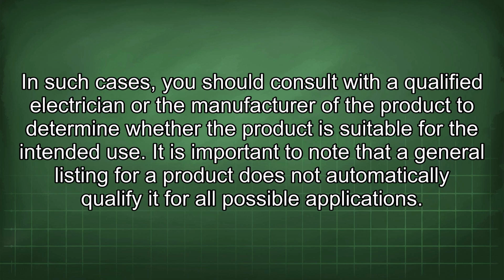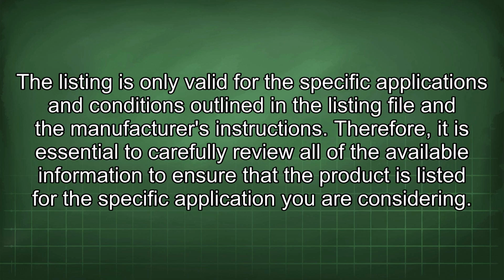It is important to note that a general listing for a product does not automatically qualify it for all possible applications. The listing is only valid for the specific applications and conditions outlined in the listing file and the manufacturer's instructions. Therefore, it is essential to carefully review all of the available information to ensure that the product is listed for the specific application you are considering.